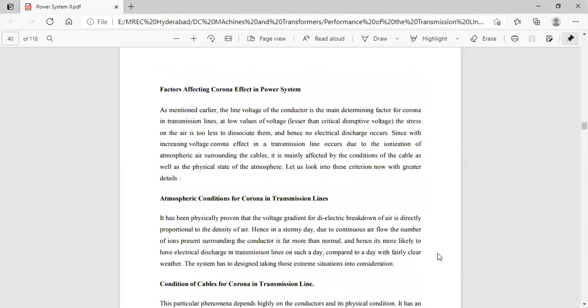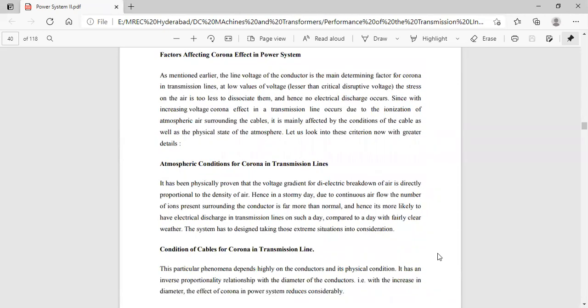The factors affecting corona effect in power systems are: the line voltage of the conductor is the main determining factor for corona in transmission lines. At a low value of voltage, the stress on the air is too little to dissociate it, and hence no electrical discharge occurs. With increasing voltage, corona effect in the transmission line occurs due to the ionization of the atmospheric air surrounding the cables. It is mainly affected by the conditions of the cables as well as the physical state of the atmosphere. Let us look into this criterion now in greater detail.